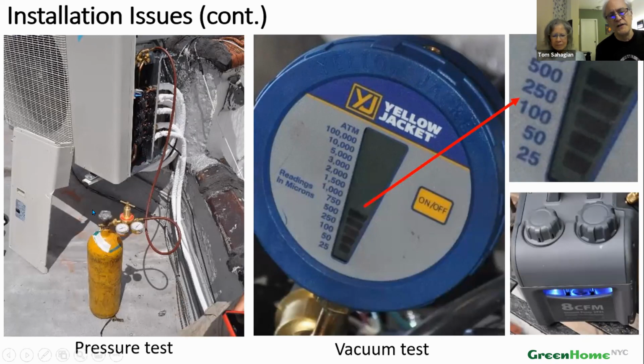Three examples here. When you're doing the pressure test, the good news is that they included the nitrogen in the test. Some contractors do not. But they used the regulator pressure sensors to establish the pressure, and they're not really made for that. And so they had to basically redo it with the proper equipment, which I'll show you in a minute. Then there's a vacuum test that also has to be done to get rid of a bunch of bad stuff that might be inside the pipes. And this particular manufacturer specifies a vacuum of under 500 microns for at least 4 hours.